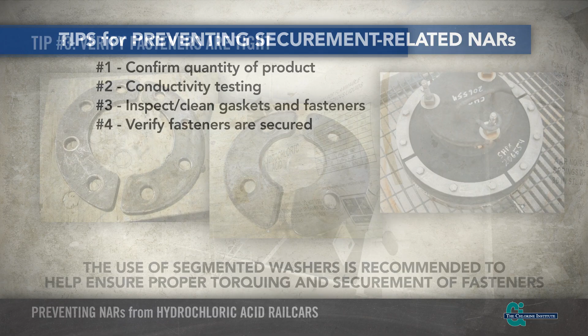It is important to ensure that the tank car's pressure relief device is closed and properly secured. Either of two types of relief devices may be installed on the railcar: a pressure relief valve or a rupture disc, as shown here. Two types of rupture discs are acceptable for use in hydrochloric acid service. An example of a polyphenylene sulfide, such as Ryton, rupture disc with optional Teflon lining is shown on the top.